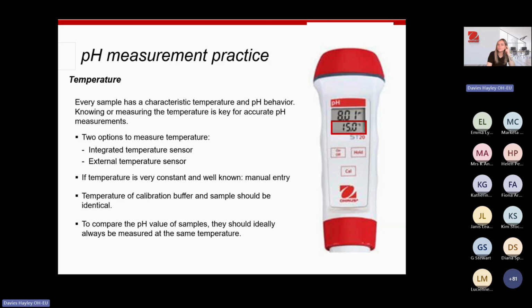Temperature. We did touch briefly on the fact that you do get electrodes that have an integrated temperature sensor. This is because pH is directly affected by temperature. So knowing the temperature of your sample is critical for accurate readings. There are two ways you can do this. You can have an electrode that has an integrated temperature sensor, which would be in the shaft with the measurement and the reference electrode, or you can use an external temperature sensor. If you're using an external temperature sensor, and you know the temperature of the sample, you may need to manually enter the temperature on your pH meter.